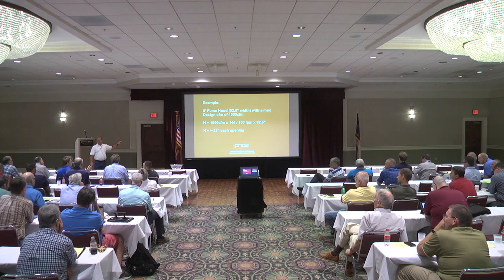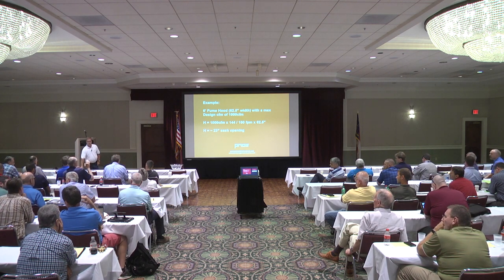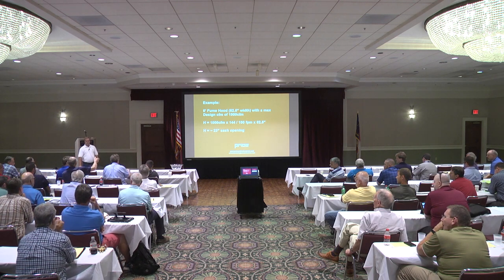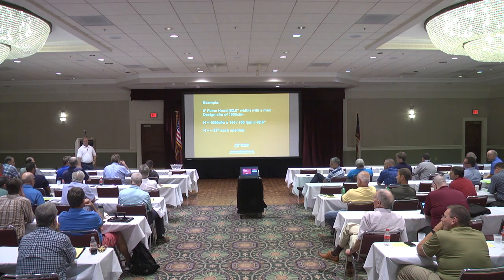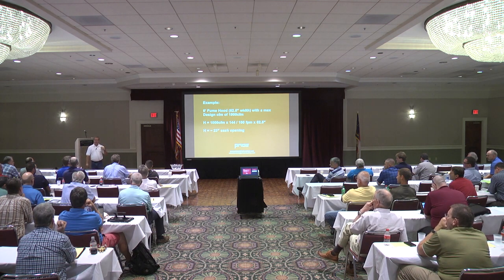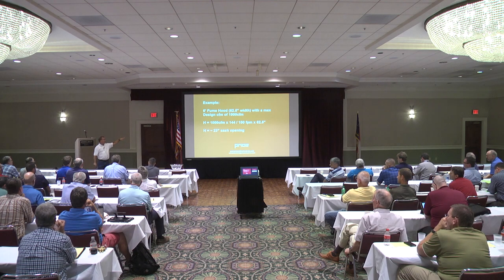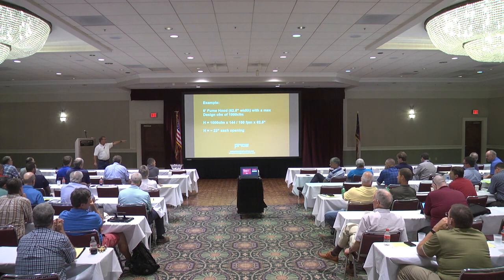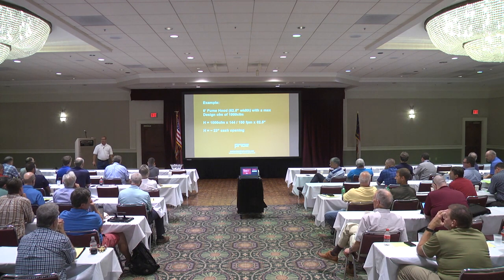Most times, and if somebody can disagree with it, but most of the time we don't have that kind of information come from the design team. We'll see 1,000 CFM, and we know the standard is 18 inches. But I have to know that going in, because I have to set this fume hood up for 100 feet per minute, 1,000 CFM. So the only way I can do that is by determining through that equation what this maximum sash height is. Are they telling you 100 feet per minute? Yes. Are you assuming I'm being told?